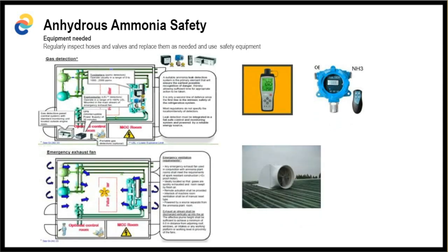At least one ammonia detector, as best practice, shall be provided in the room or area. Alarms shall be activated whenever the refrigerant vapor exceeds the permissible exposure limit. So normally for people it's around 50 ppm. Audible and visual alarms shall be provided inside the room to warn when the alarm has activated. Access to the room is restricted to authorized personnel and emergency responders only. In connection with the leak detector, purge fans shall also respond automatically to the refrigerant concentration detection system.